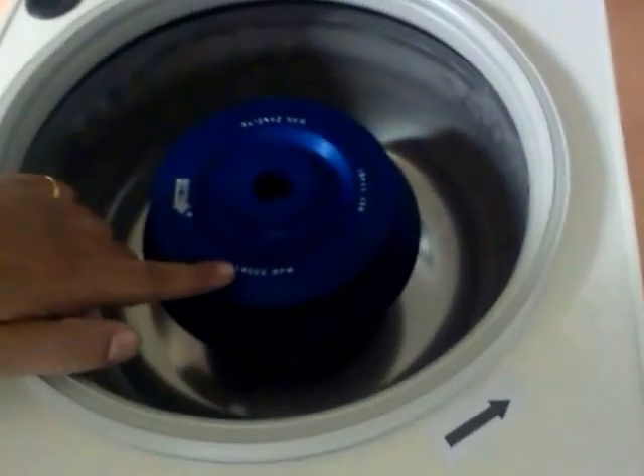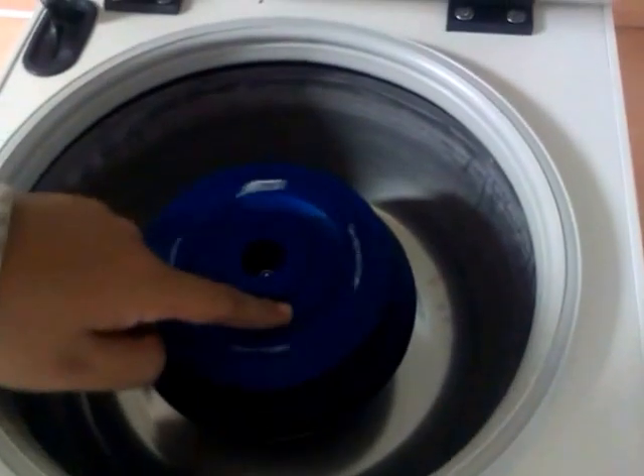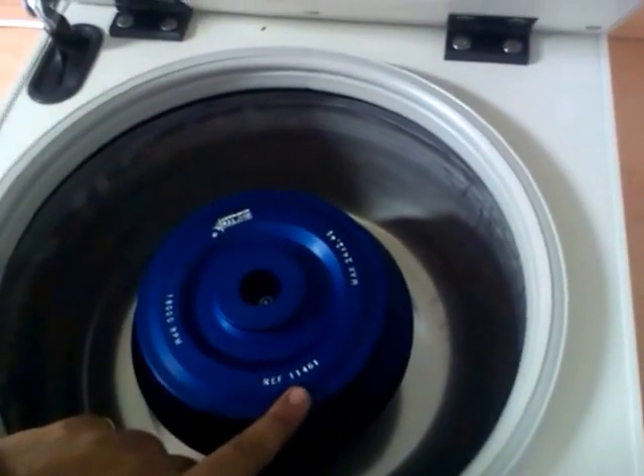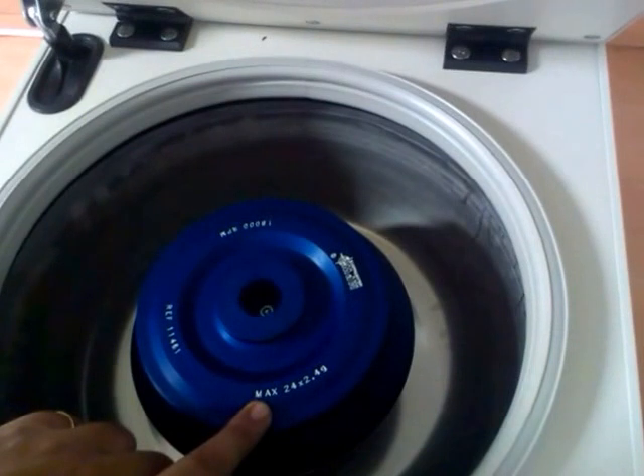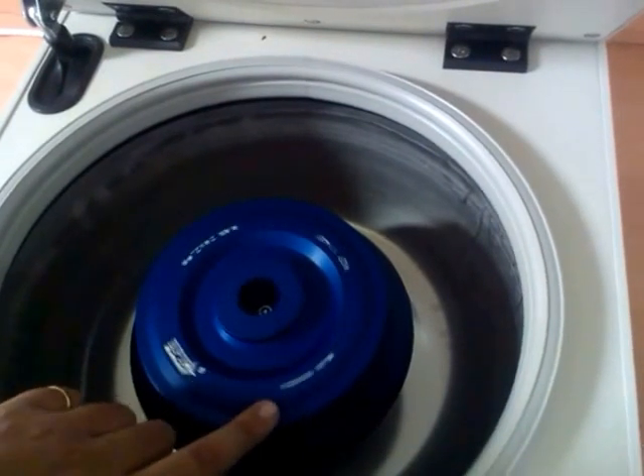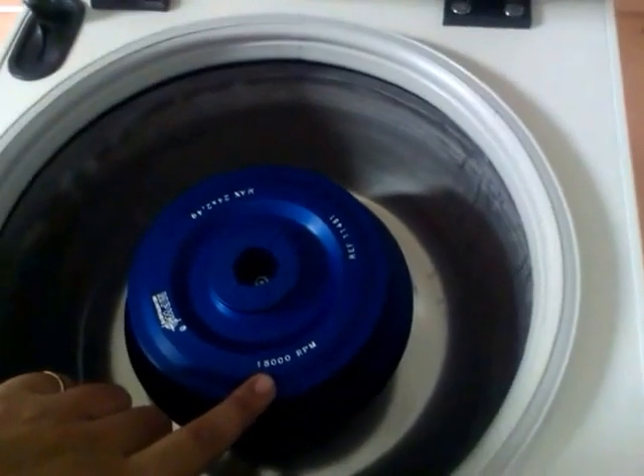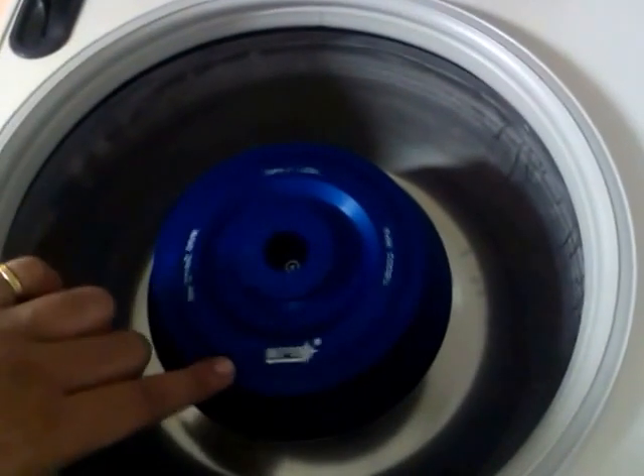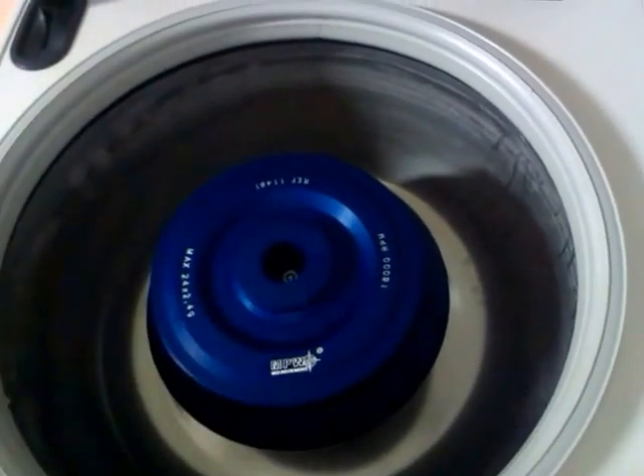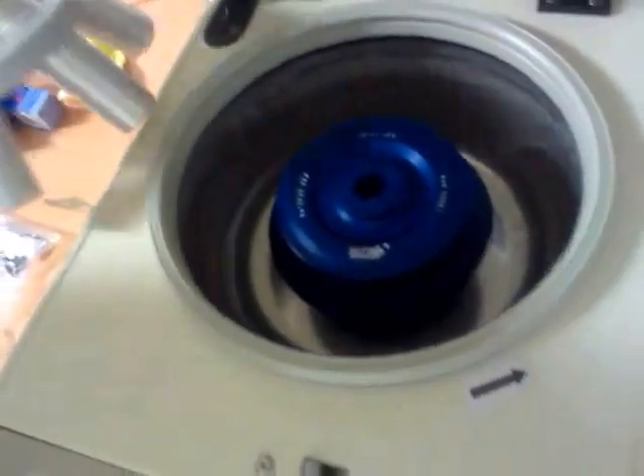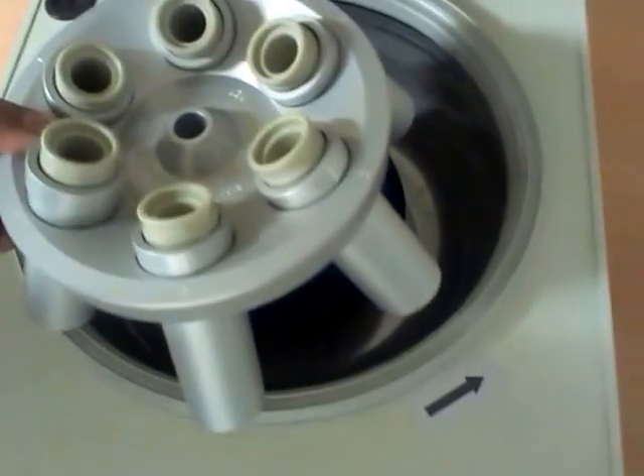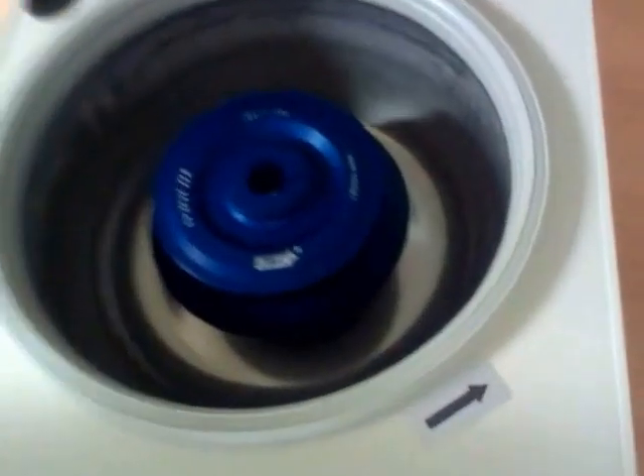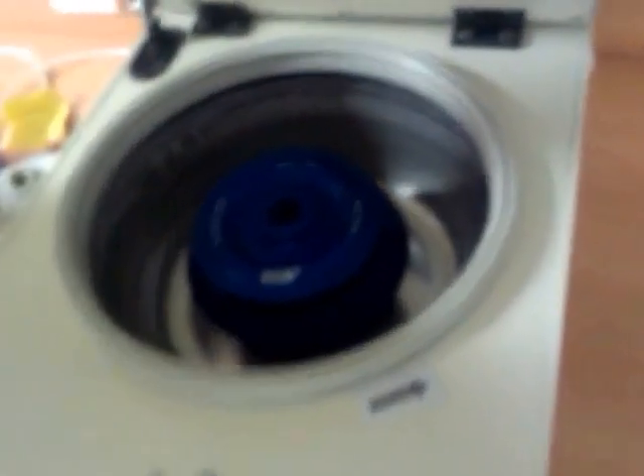Then this is the rotor. We have different rotors available here, on each of which the catalog number of the rotor is mentioned, what is the maximum G value it can withstand, and what is the maximum RPM it can go up to. So this particular one is for the 1.5 ml rotor. Similarly, we have rotors for 15 and 50 ml centrifuge tubes, and with different adapters. The machine is very soundless, vibration free.